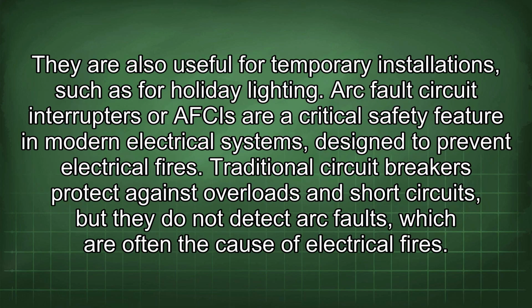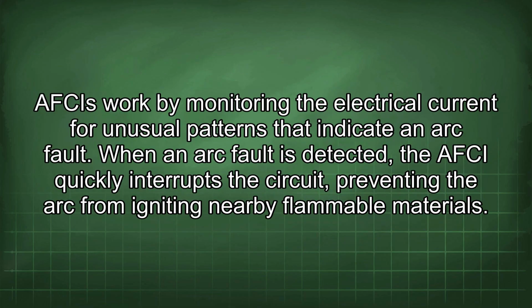They are also useful for temporary installations, such as for holiday lighting. Arc fault circuit interrupters, or AFCIs, are a critical safety feature in modern electrical systems, designed to prevent electrical fires. Traditional circuit breakers protect against overloads and short circuits, but they do not detect arc faults, which are often the cause of electrical fires. AFCIs work by monitoring the electrical current for unusual patterns that indicate an arc fault. When an arc fault is detected, the AFCI quickly interrupts the circuit, preventing the arc from igniting nearby flammable materials.